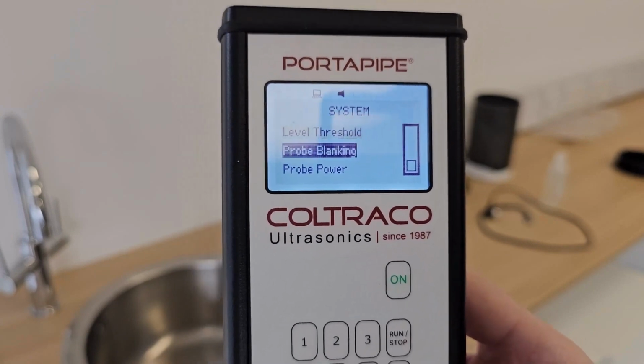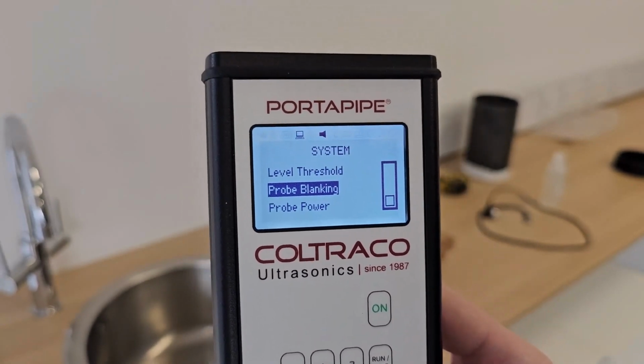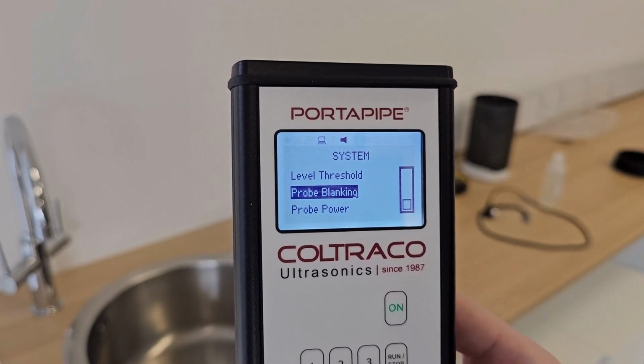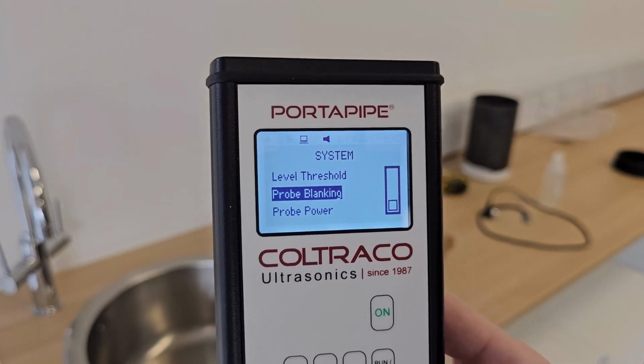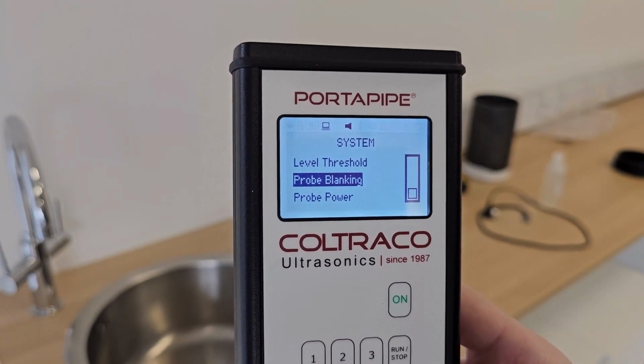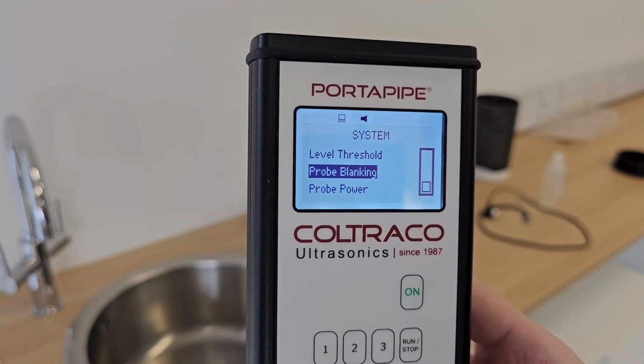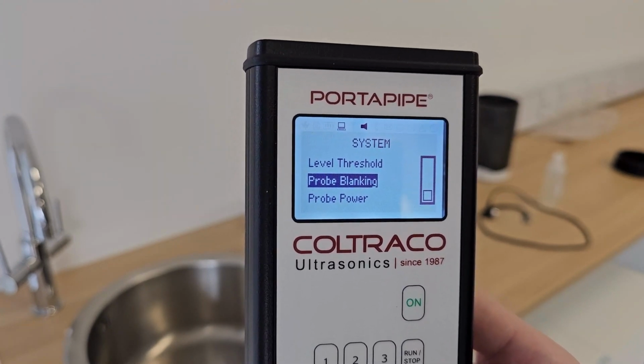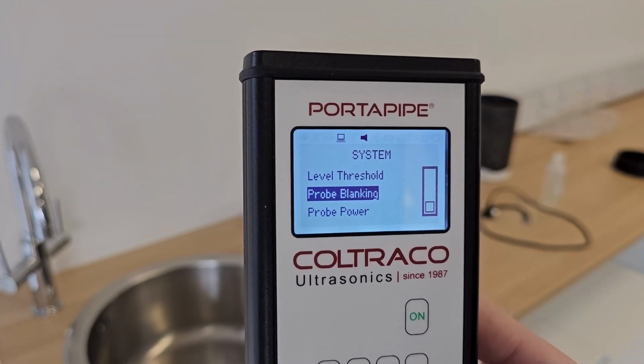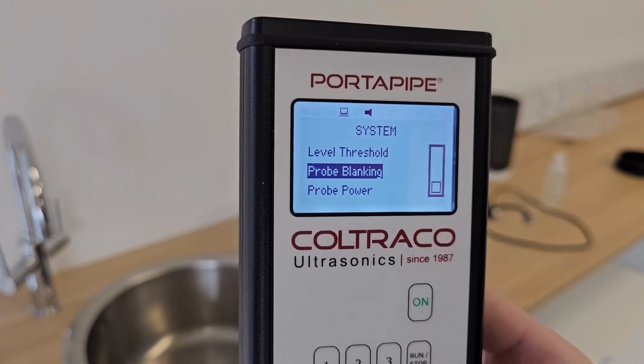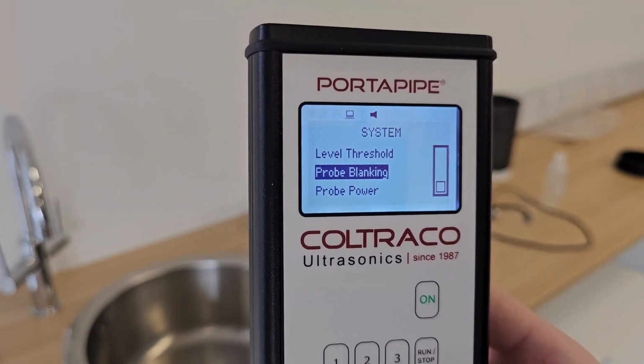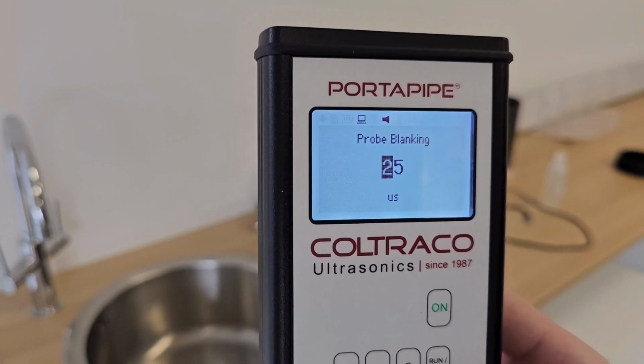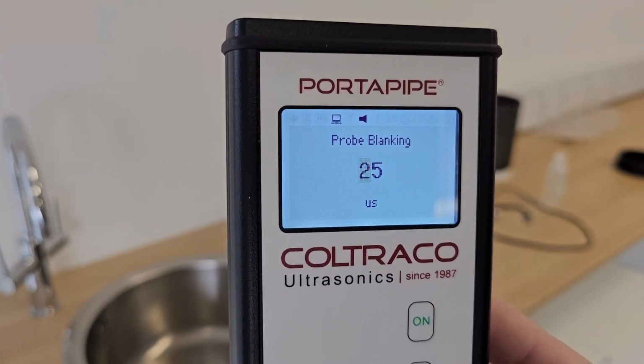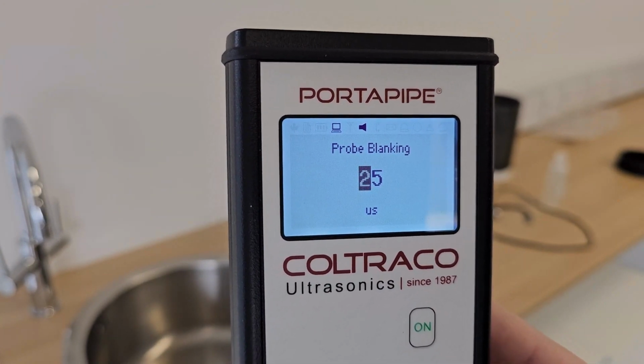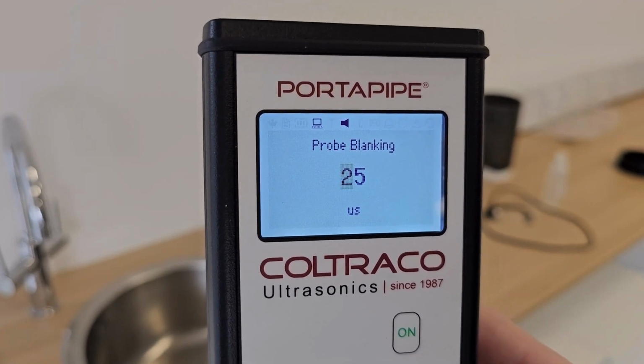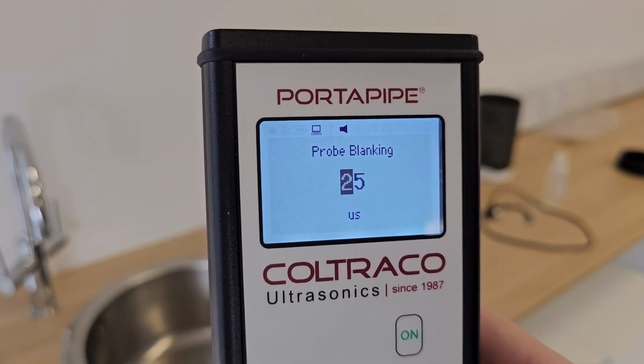And then we have probe blanking, which is a period at the start of the measurement where the device does not listen. This is to avoid interference with your measurements from things like the walls of the container ringing, which they can do, particularly with metal containers, and we don't want that to interfere with our measurement and give us false levels. So I have this set to 25 microseconds, which is a pretty good baseline, and again you may need to adjust that, and we can talk about that more if we have to do that later.